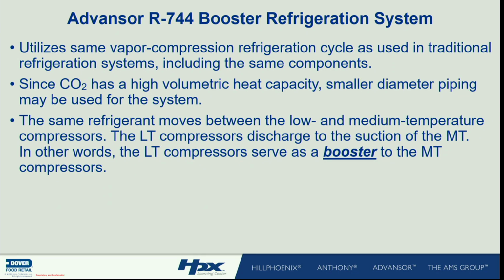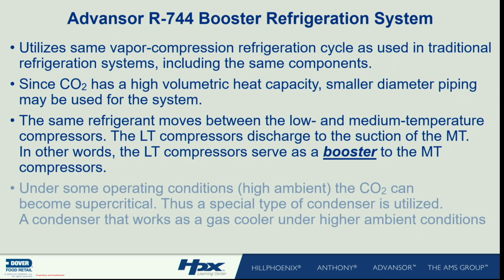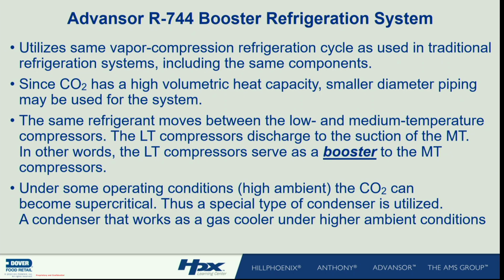Let's say it's 70 degrees outside. Is that rack transcritical? No, it has to be above 87.7 for that. But is it a booster? Yes. If it's 95 degrees outside, is it transcritical? Yes. Is it a booster? Yes. If it's 30 degrees outside, is it transcritical? No. Is it a booster? Yes. Everybody get my point? It's always a booster, that's the technology. And at certain conditions, we're going to talk about those conditions.